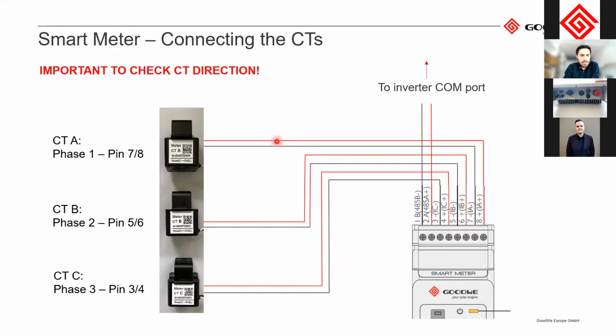Here you see the exact connection for each CT. So for phase 1, you have CTA, for phase 2, you have CTB, and for phase 3, you have CTC. As you see here, for phase 1, you will connect to the 7 and 8, so you will start from right to left when you go with the phases. And the last 2 here will be connected with RS-485 directly to the COM port of the inverter.